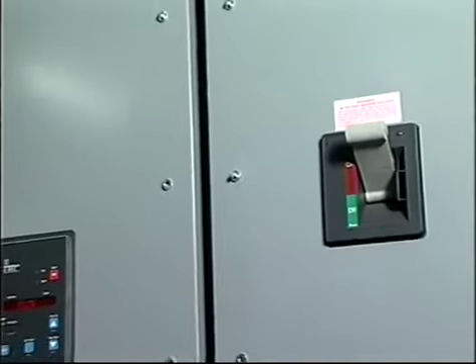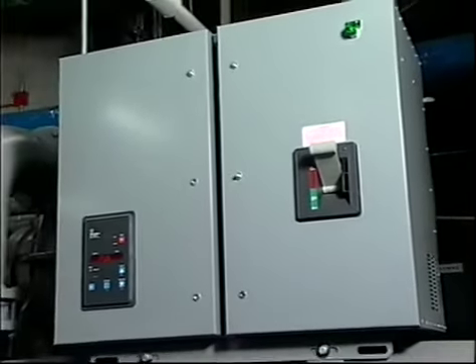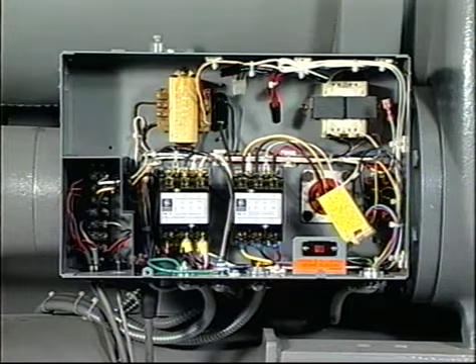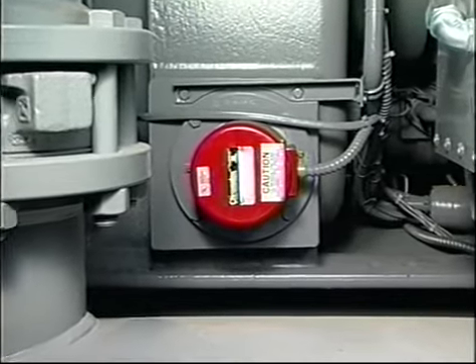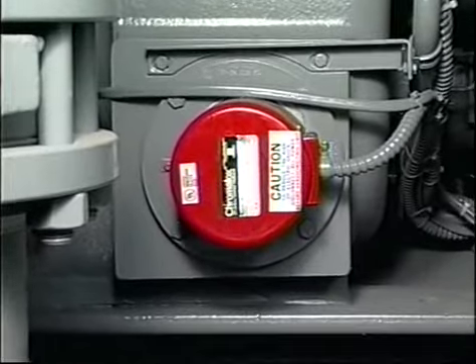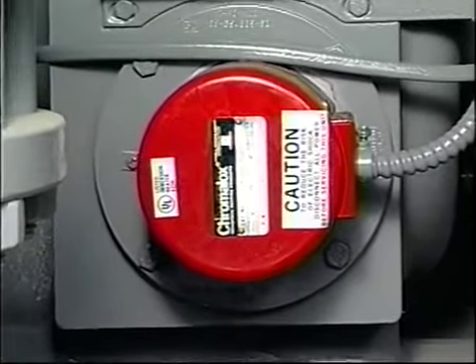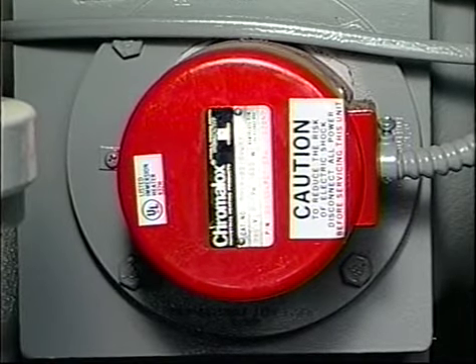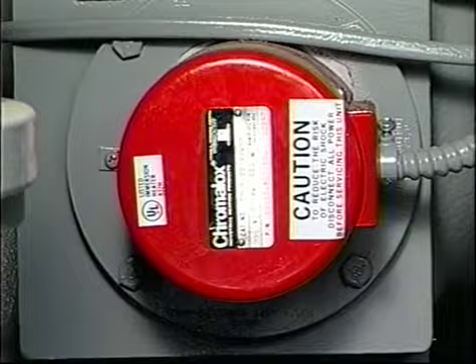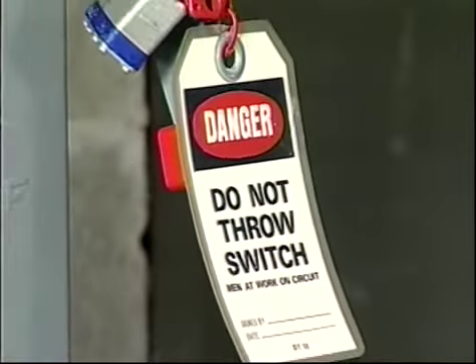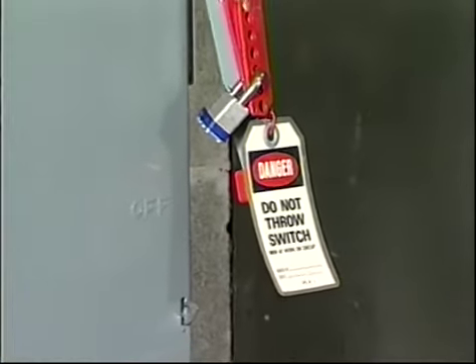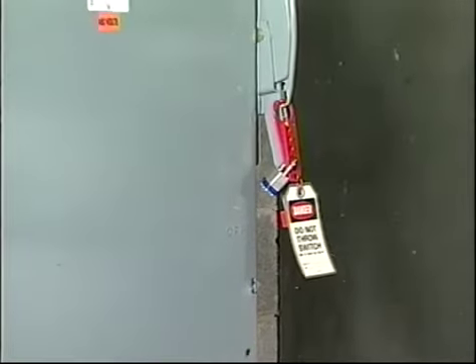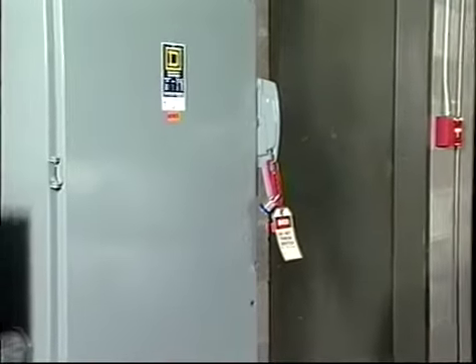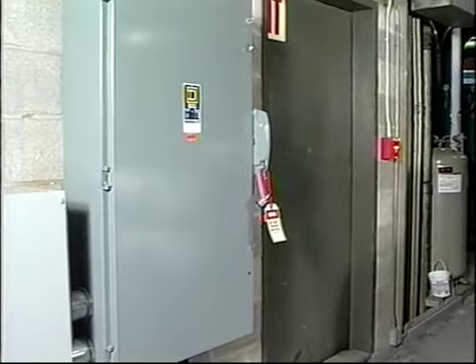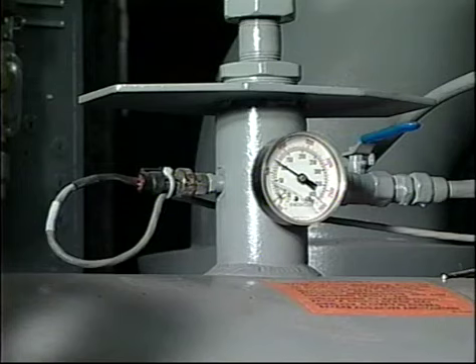Finally, don't work on electrical components which include the starters, switches, control panel, and the oil heater unit unless you are positive that all of the power is off and that there are no residual voltages in capacitors or solid-state parts to zap you. If you are going to fix electrical circuits, tag and padlock them open. If you must interrupt your work, make sure that all circuits are off before resuming work. Don't remove any parts while the machine is running or under pressure.